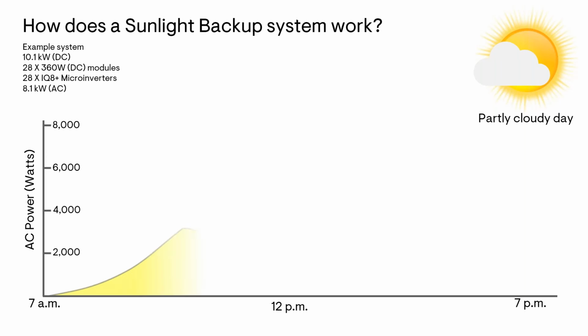On a partly cloudy day, the available solar power is going to fluctuate a lot as clouds periodically block the sun. If the home's power demand ever exceeds the power of the solar system, then of course the microgrid is going to shut down. After a few seconds have passed, the system is going to attempt to restart again. And if the available power can handle it, then it'll work. But if the power demand still exceeds the available solar power, it won't be able to start up. It will attempt repeatedly, multiple times over increasing time intervals, to allow the solar system power to hopefully increase along with the irradiance. And hopefully the homeowner will also realize the system is trying to start and will turn off as many loads as possible.